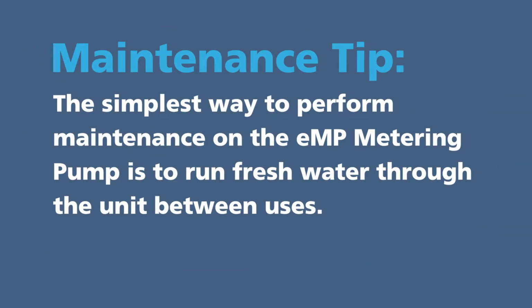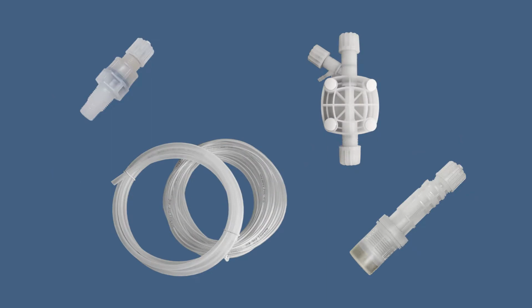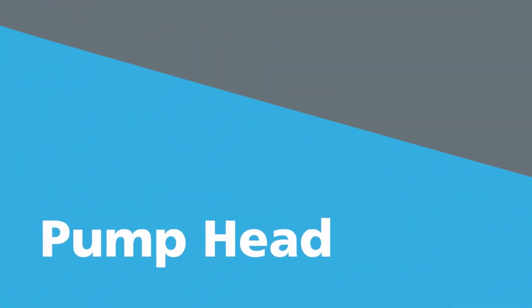Maintenance tip. The simplest way to perform maintenance on the eMP metering pump is to run fresh water through the unit between uses. This helps prevent buildup inside the foot filter, pump head, injection valve, and tubing, allowing for these components to last longer. Pump head.